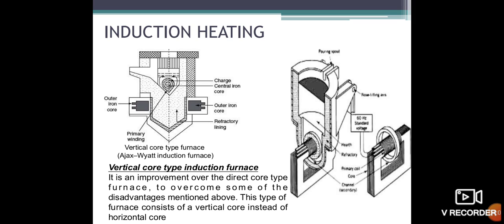So even if the furnace is not functioning, a low voltage is maintained across the primary with the help of an auto transformer, which circulates the current and thus keeps the charge in the molten state. Now the additional charge to be melted is poured into the furnace. The primary is given the AC supply, causing heavy current in the material housed in the V channel. Thus heat is produced, which is utilized for melting the charge, and circulation of the molten metal takes place in the V channel.